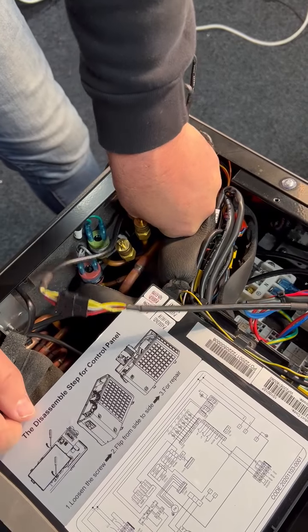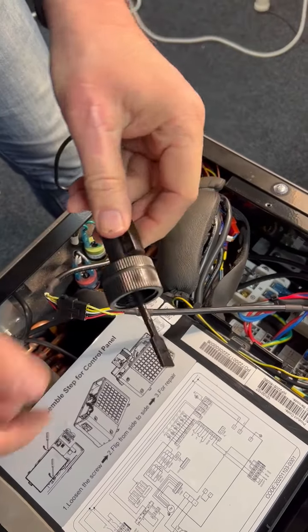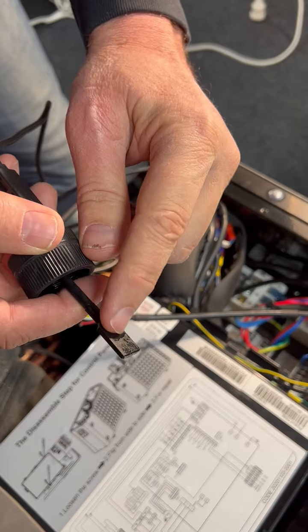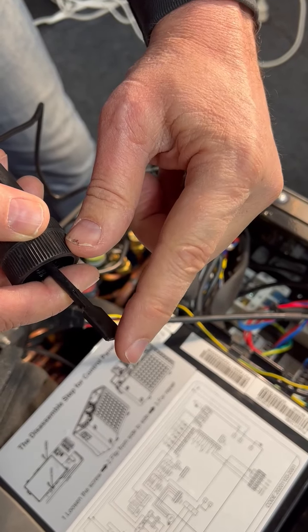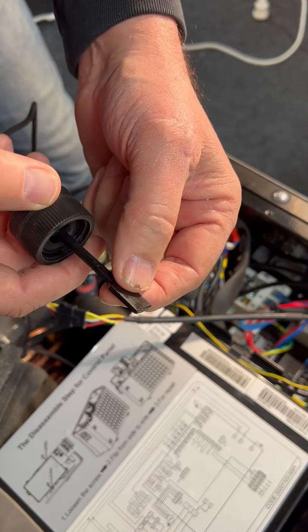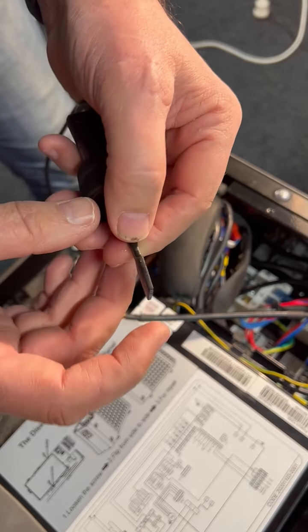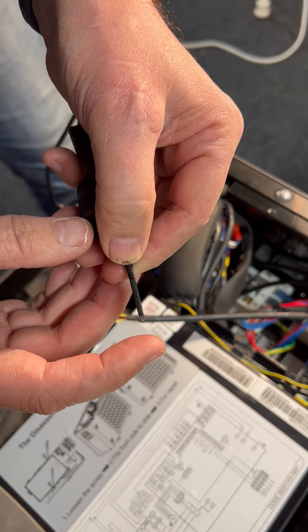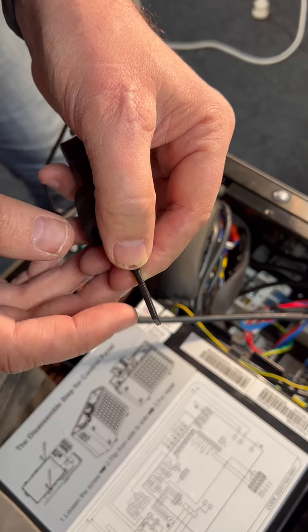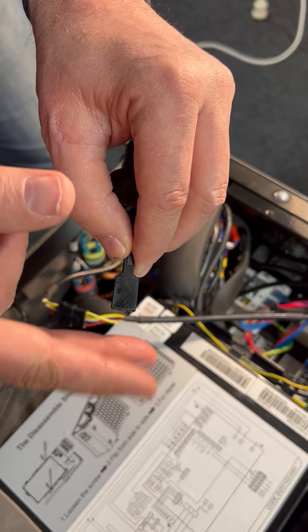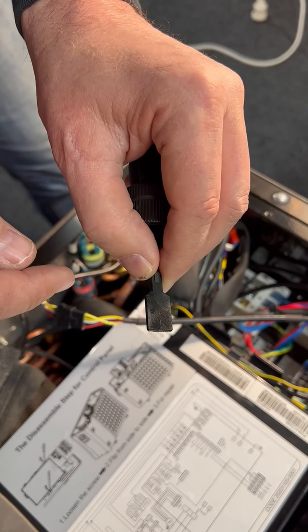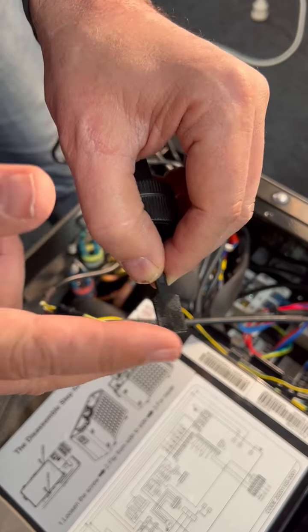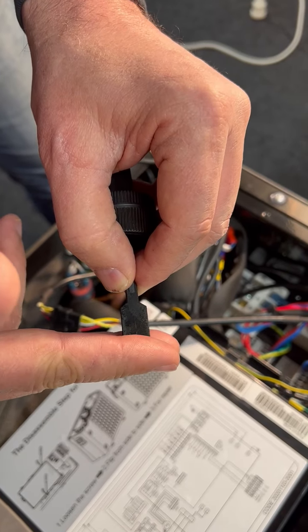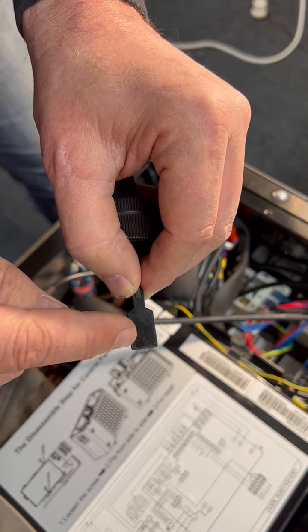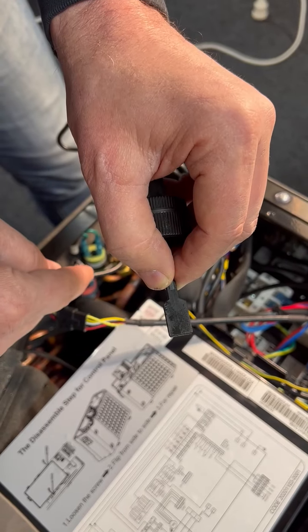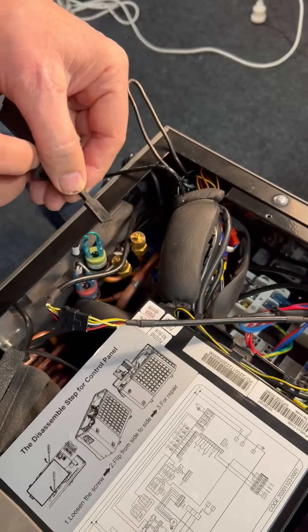Now, in saying that, in some of the smaller heat pumps and the larger heat pumps require bigger paddles. So the brand new flow switch that you will get might have a longer paddle. So what you do is you compare the paddles, and you may have to cut the paddles to size. So whatever you take out and whatever you put in, the new one, you just cut the paddles so it's exactly the same length as this. And then we know it's not going to scrape on the bottom or get caught. That's it.